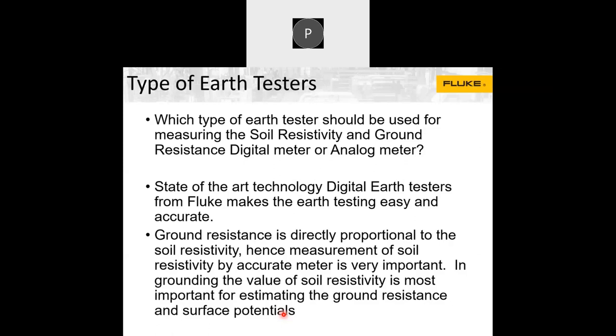State-of-the-art digital earth testers are used for accurate measurement. You can use a digital earth tester or an analog one, but each has its own advantages and disadvantages. Ground resistance is directly proportional to soil resistivity, meaning you first have to find the soil resistivity and then design accordingly so you can achieve the best resistance levels.